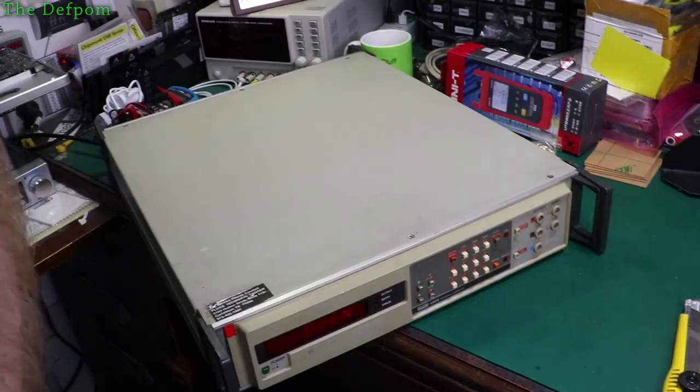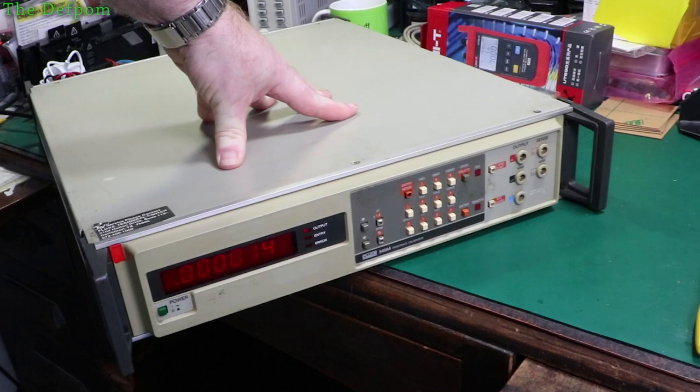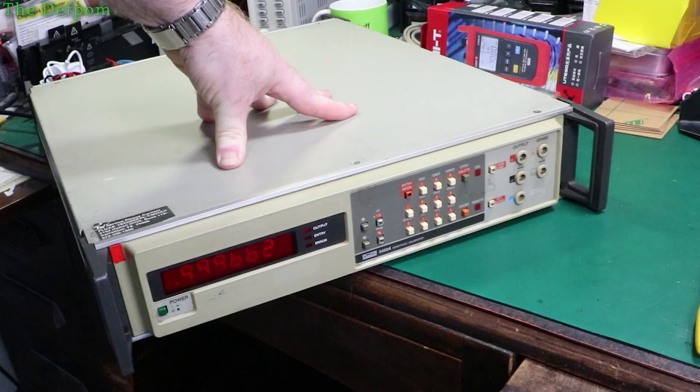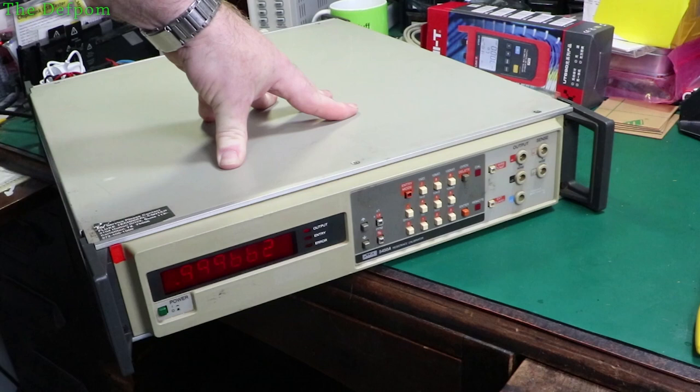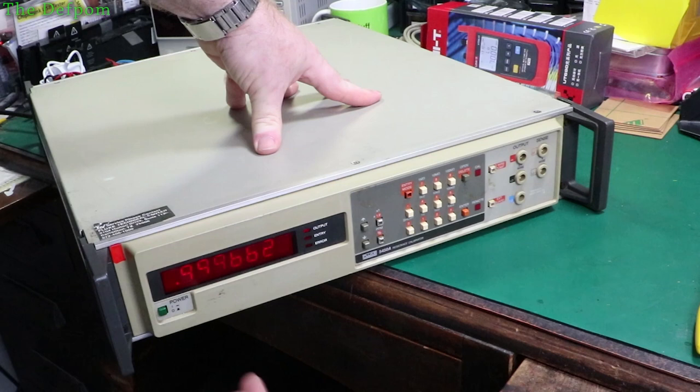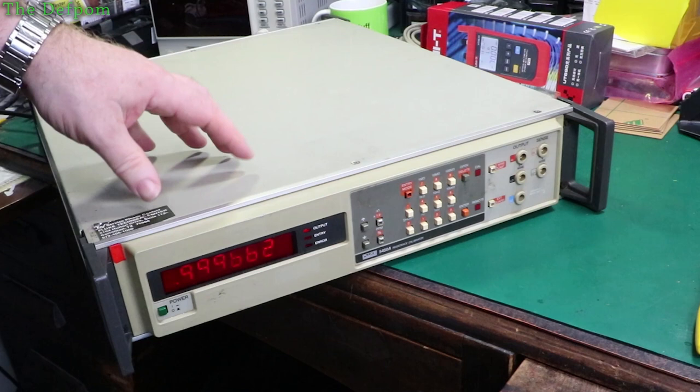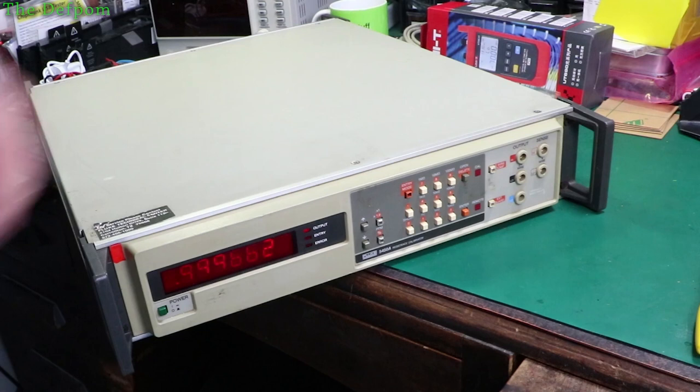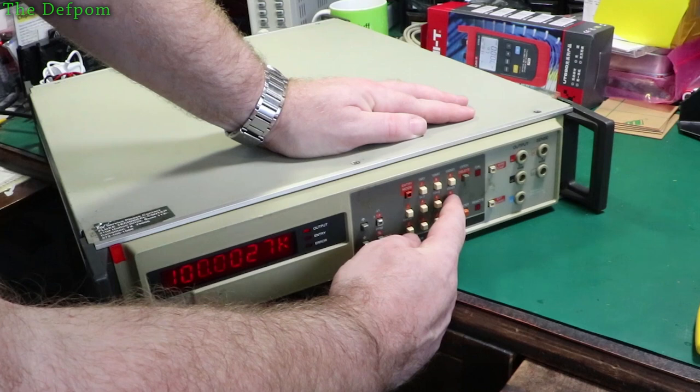Looks like it does. The question is, does it work? So let's do short. Supposedly one ohm. So these are the calibrated values of the resistors that are inside this unit. Okay, so this isn't a selectable resistance box. Like you could say, I want 2.76K. No, you just put in 1 or 1.9 of each type and it will tell you what that resistance value is on the display here, which has been calibrated. You know, it's been measured and recorded in this memory. So what you see on here should be what you get on a piece of test instrument when you're doing the precision checks. So let's go through them. It's supposed to be 10, 100, 1K. This doesn't have a light on, eh? Let's see if it's easier. 10K. So all I've really got to do is check on these to make sure they look about right. It's got two wire, four wire stuff like that, because it is a precision instrument, supposed to be for doing calibrations.